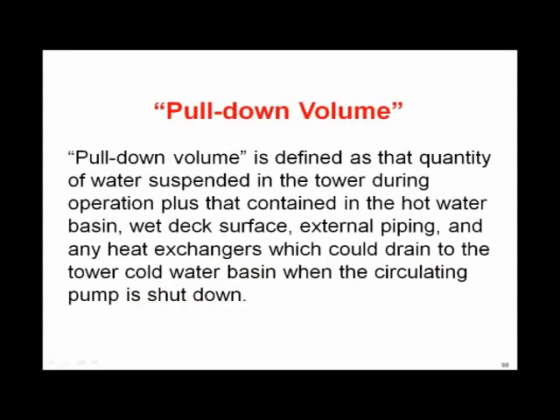Tower floods at shutoff. What would cause that? There's something on anybody's tower called pull down volume. That's the amount of water in the fill and the hot decks, a little bit of overhead piping. And the sump of the tower is designed to hold that pull down volume. It'll hold it nicely. So that's the design.